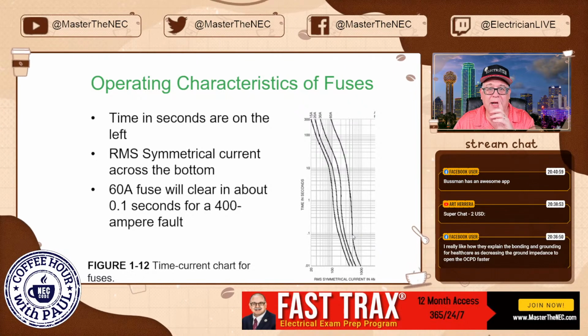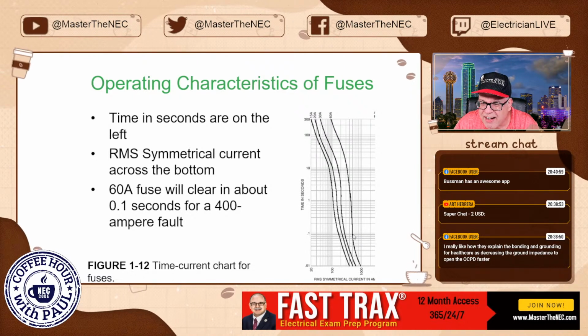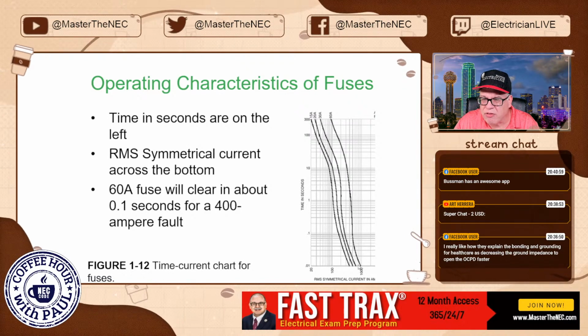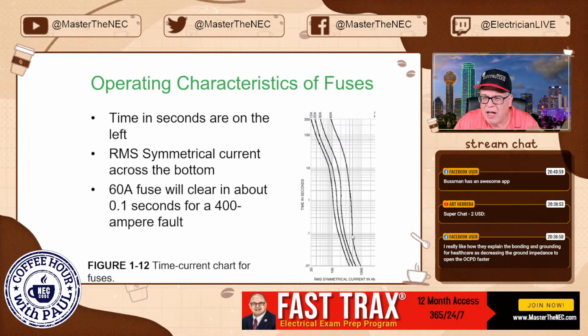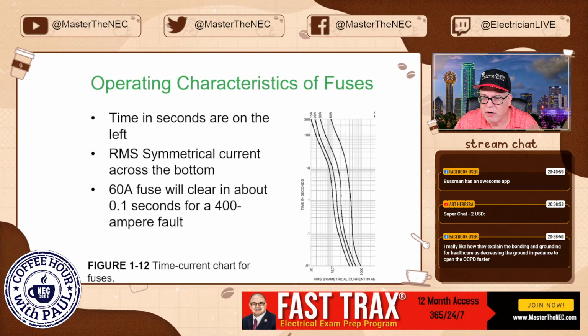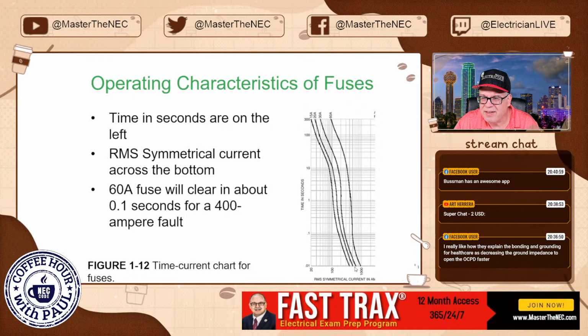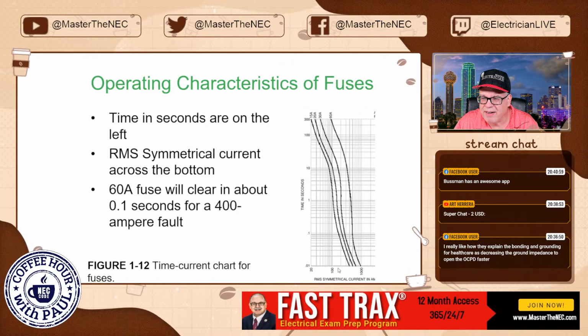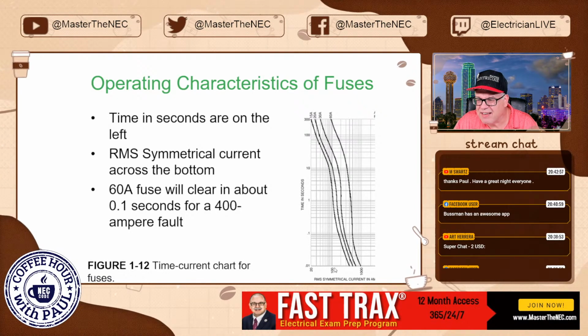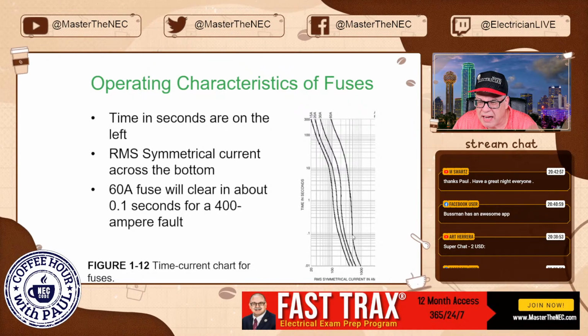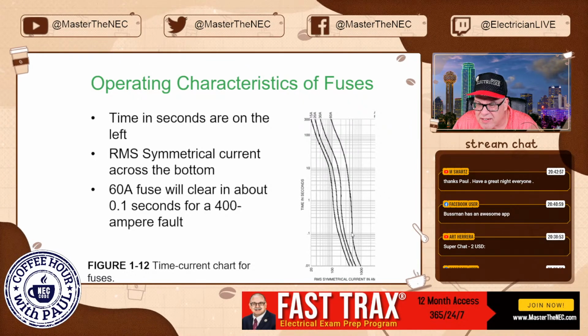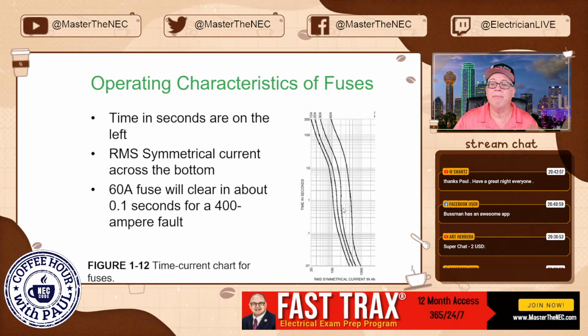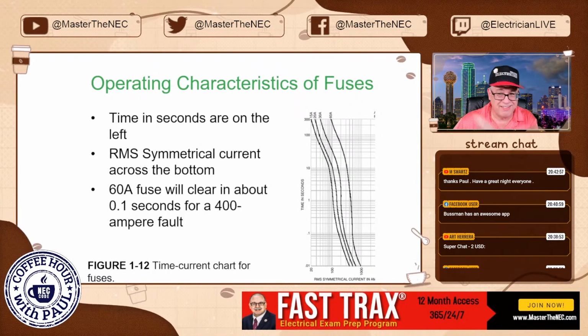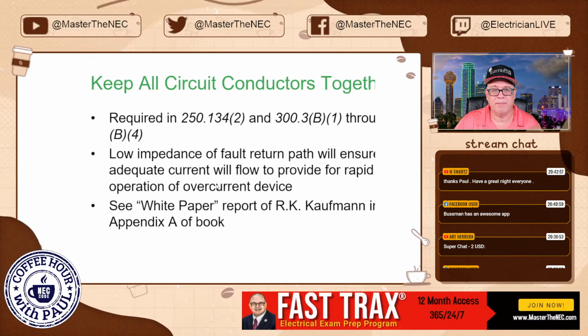Hopefully y'all can see my pointer. I forgot to ask anybody if you could see my mouse. So right here, see right here? So right here at 0.01, it's 1,000. But right here at 0.1, you'll see that it's right here. If you count up, 100, 200, 300, 400. Looks like right here, 400 ampere. I don't know what this breakout is. I can't even see it with my eyes. My eyes are so blind here. But right about right there, it looks like that's where the 60 would be. So it looks like that must be 1, 2, 3, 4. I don't know. Anyway, let the manufacturer do it for you. This stuff is confusing as it is, okay? I am no expert. All right.